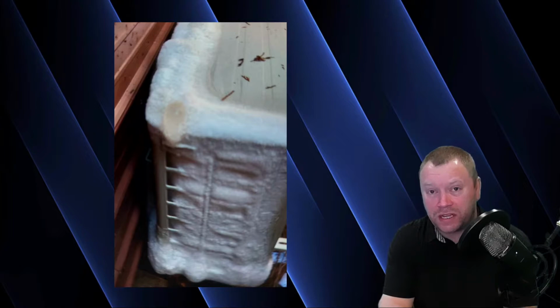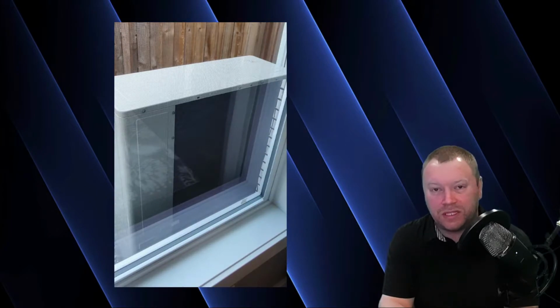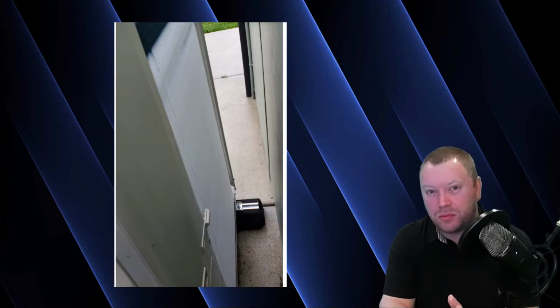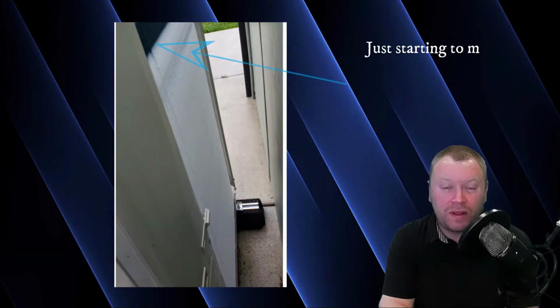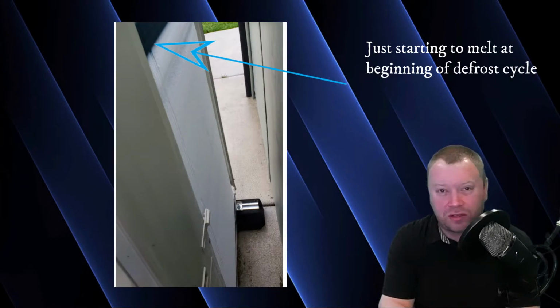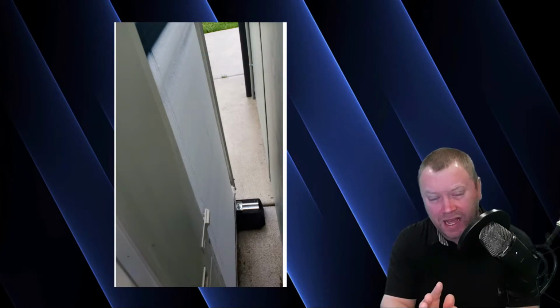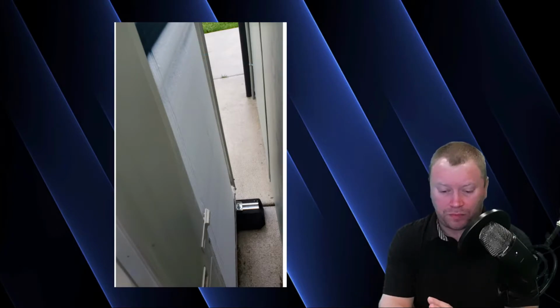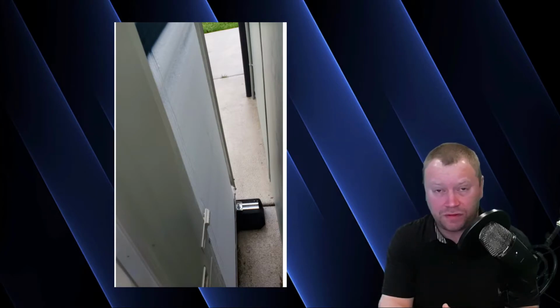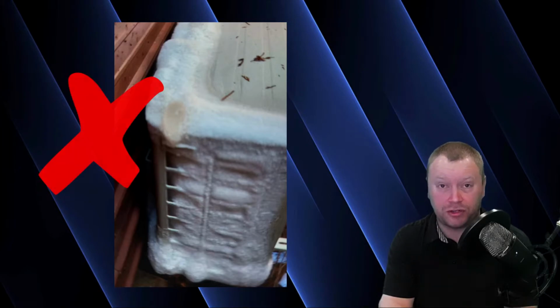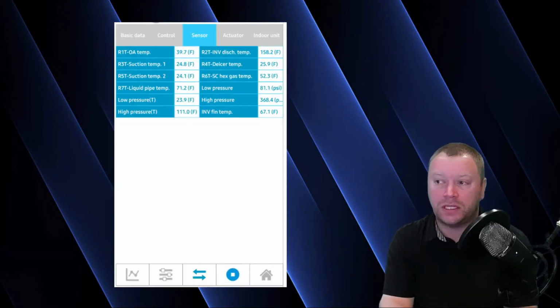Now, on a second note, this time of year, we have a lot of defrost issues, or so we think. When your unit is completely defrosted, you should have a nice clean heat exchanger like this picture. This is the back of the unit that I have at my house. Nice and clean, fresh off of a defrost cycle. What it should look like right before or right when it's starting the defrost cycle is a nice thin blanket of frost. So you can see here right at the top of the unit, it just started frosting out. I had just started the defrost cycle when I snapped this picture. But you can see it's a nice thin blanket of frost. This is normal. So if you're not sure if your unit is having problems with defrost, a lot of ice buildup, then compare this picture to this picture and you can clearly see the difference. All right, so now let's take a look at the runtime.